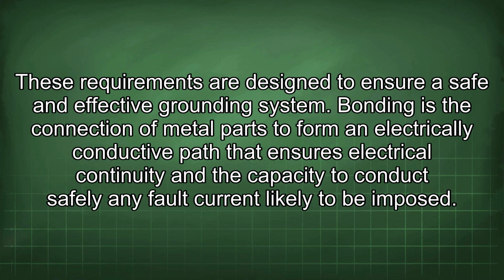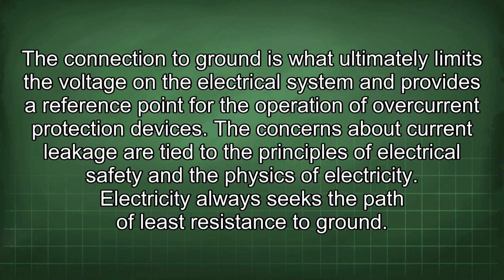Bonding is the connection of metal parts to form an electrically conductive path that ensures electrical continuity and the capacity to conduct safely any fault current likely to be imposed. The connection to ground is what ultimately limits the voltage on the electrical system and provides a reference point for the operation of overcurrent protection devices.